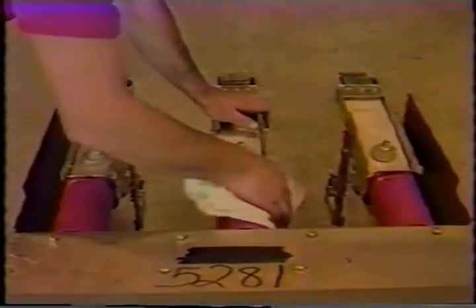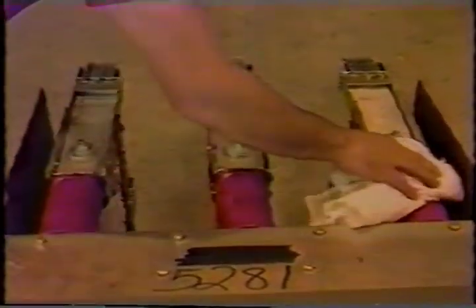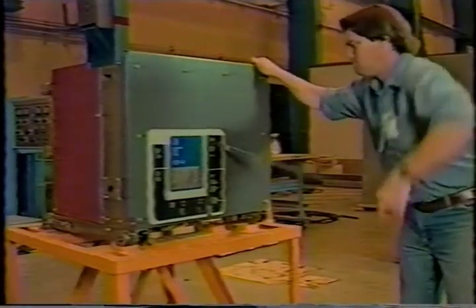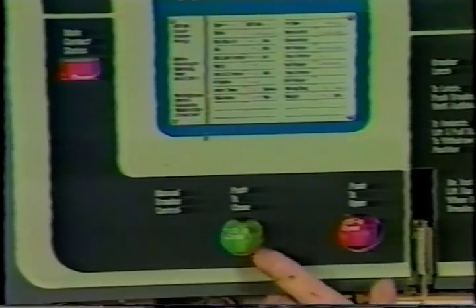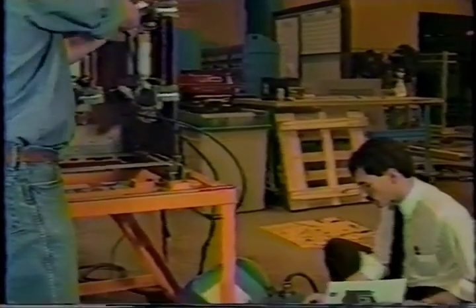Using a dry, lint-free cloth or a paper towel, clean all the insulating surfaces of the pole units. Conduct a vacuum interrupter integrity check as described in Maintenance Section 6 of the breaker instruction book. Also, check the breaker's primary and secondary insulation per Section 6. Contact erosion can be checked by viewing the moving stem of the vacuum interrupter from the rear of the breaker. Manually charge the mechanism and close the breaker. With the breaker closed, visible presence of the erosion indicator will assure adequate contact surface. Check the primary circuit resistance as described in Maintenance Section 6. The resistance should not exceed the value specified. Record the values obtained for future reference.